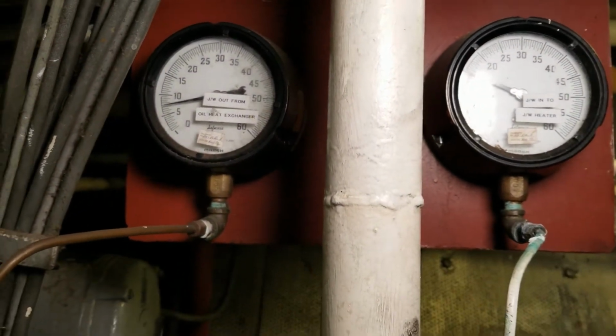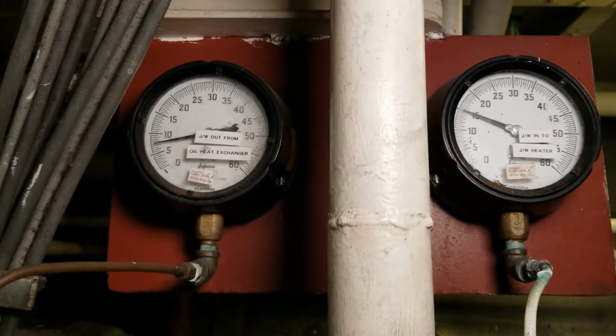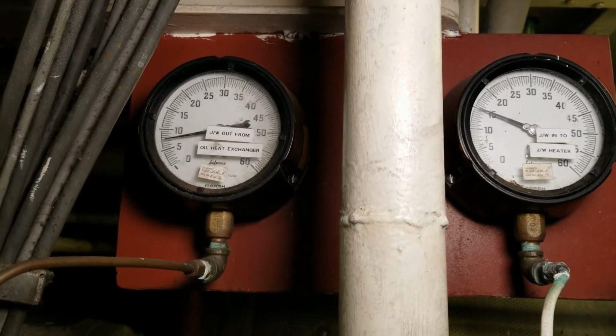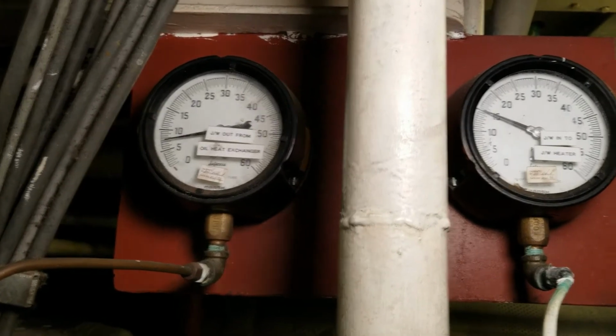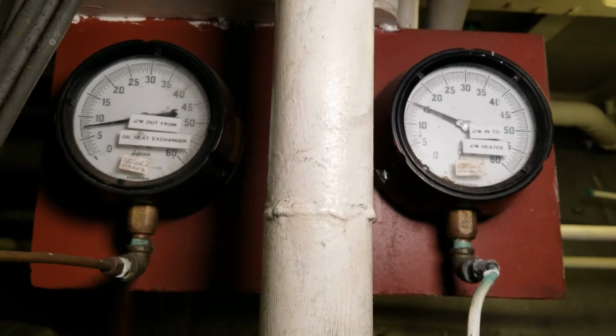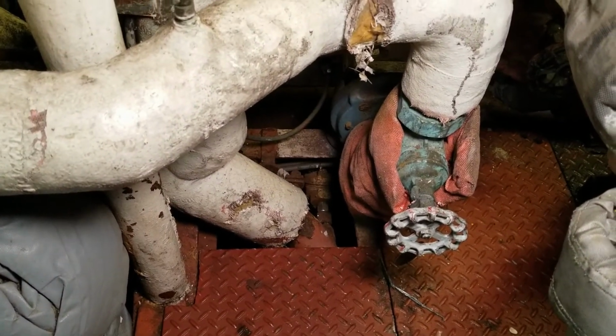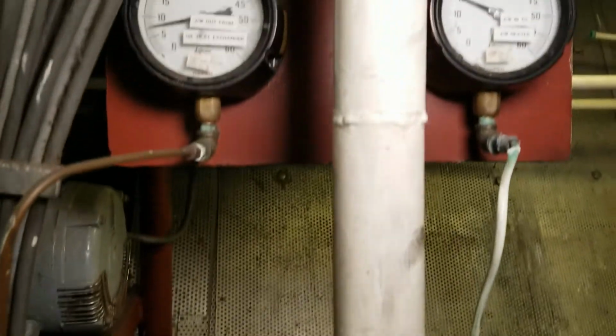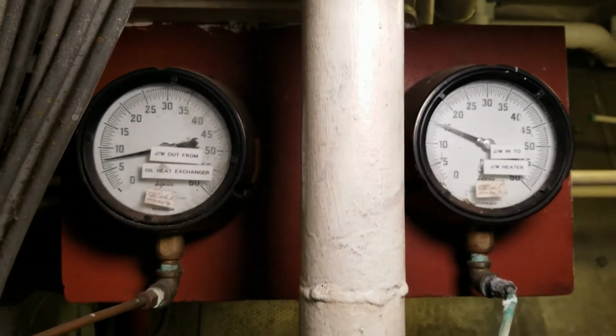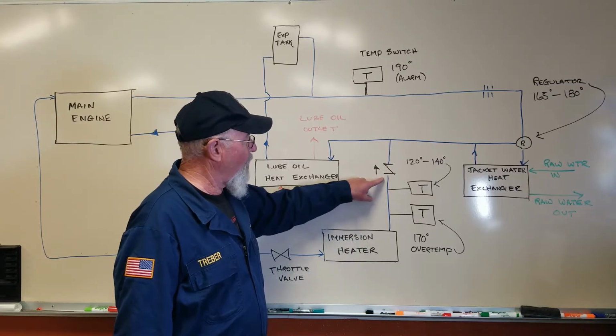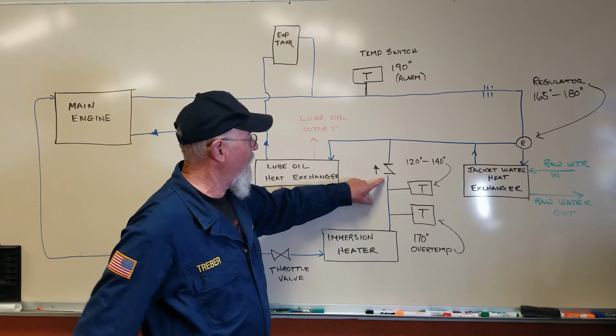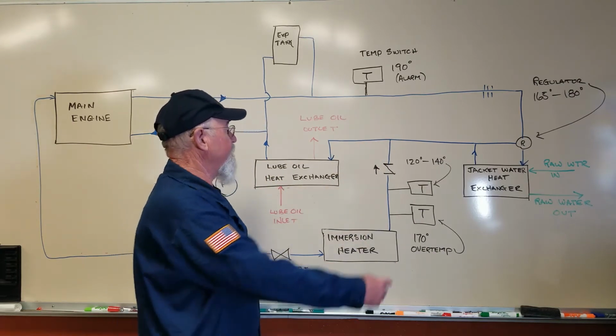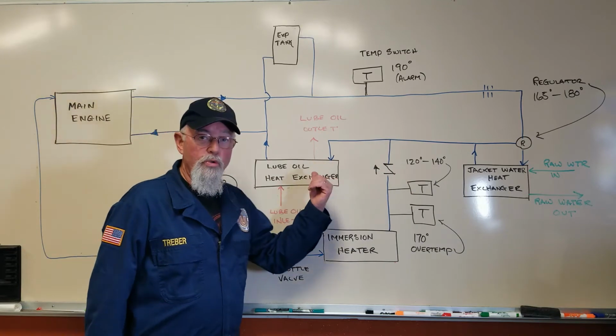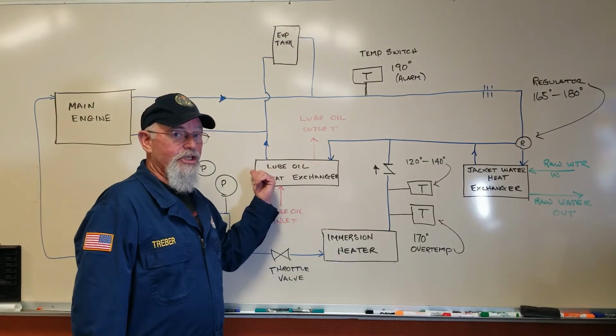So on the two pressure gauges, we're looking at maintaining a differential pressure of approximately 7 psi coming out of the heat exchanger and 15 going in. I can adjust that with the throttle valve if I need to on the discharge side of the pump, but I've already got that adjusted to maintain my desired differential pressure. Next component downstream you'll see is a check valve, a swing check valve. So it allows flow in one direction only. And now the heated jacket water is going through the heat exchanger for the lube oil system.